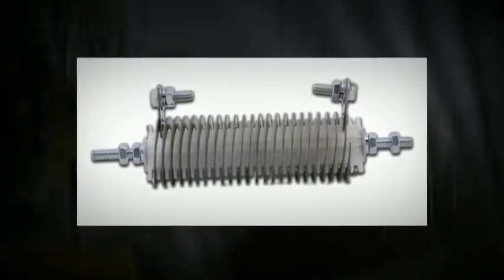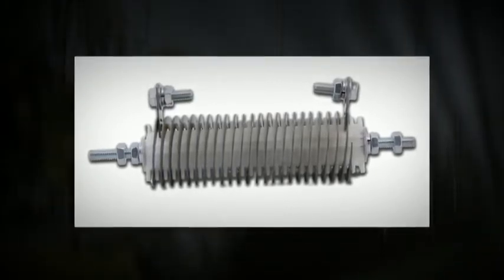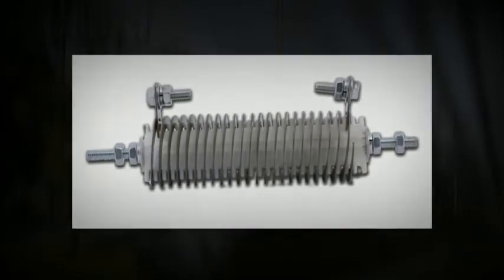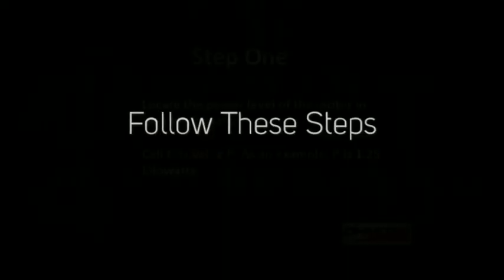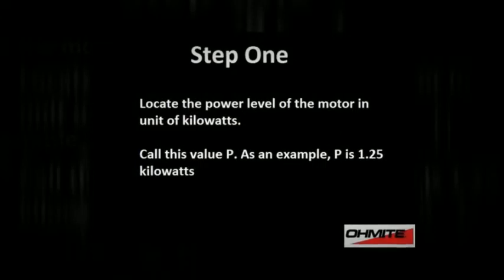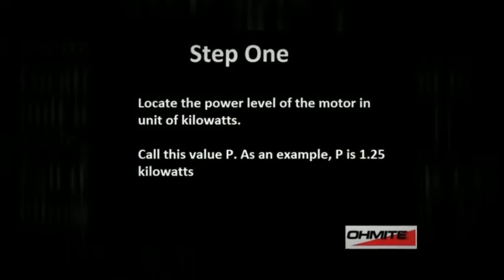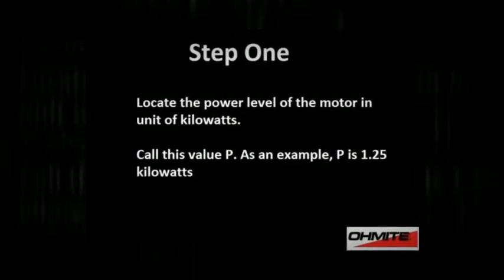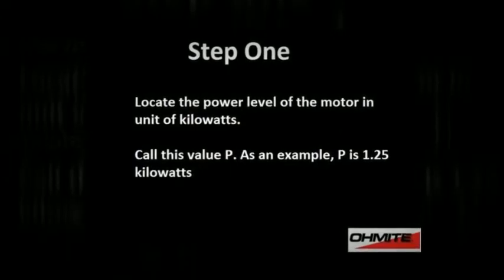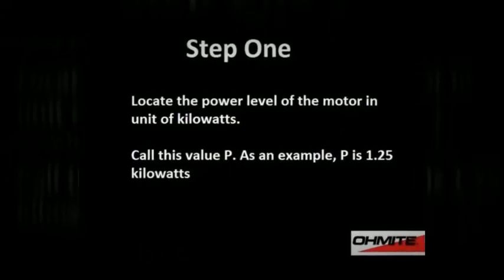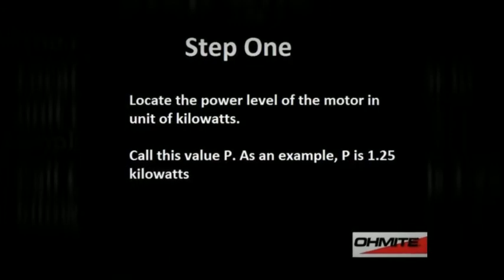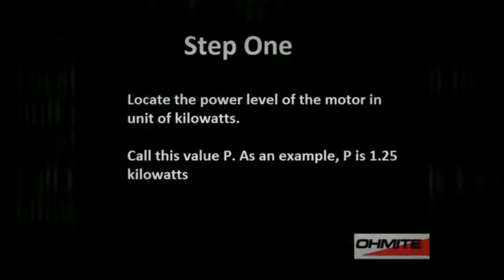To calculate the maximum dynamic brake resistance value of a small motor, follow these steps. First, locate the power level of the motor in units of kilowatts. Call this value P. As an example, P is 1.25 kilowatts.